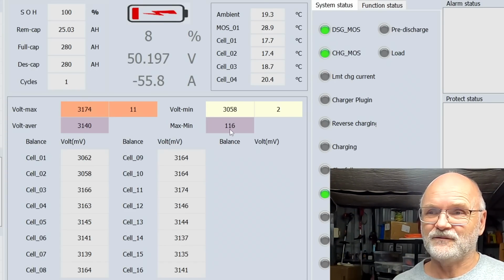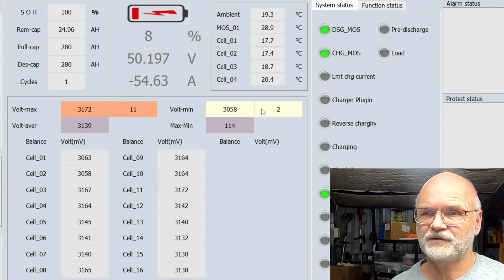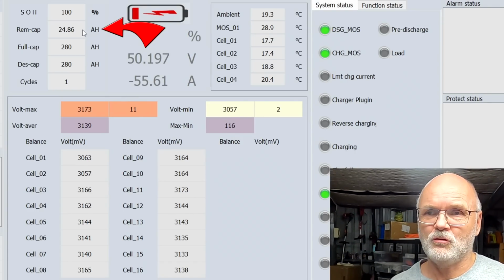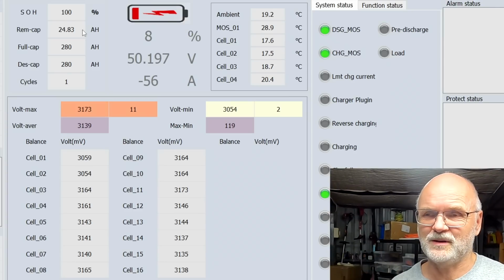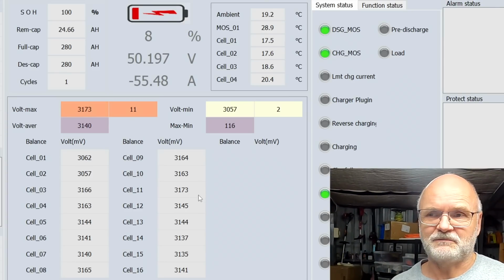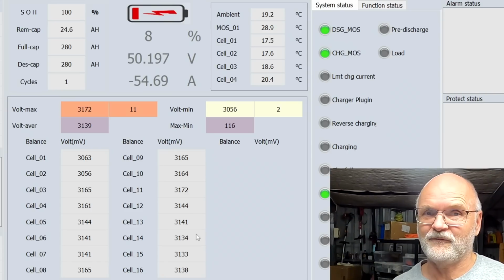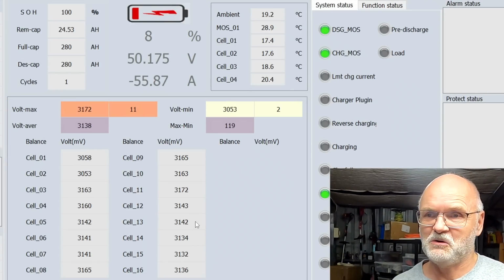We've got 117 millivolt deviation now, so cell number 11 is the highest, cell number 2 is the lowest. Got 25 ampere hours to go - this might be another 15-20 minutes maximum. So far you would not be able to tell which battery is a 304 ampere hour and which is a 280 ampere hour battery - they are all the same.